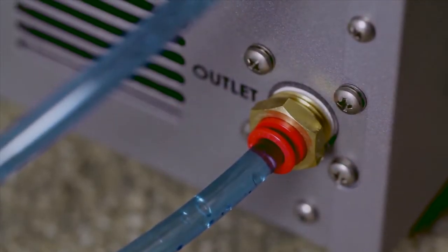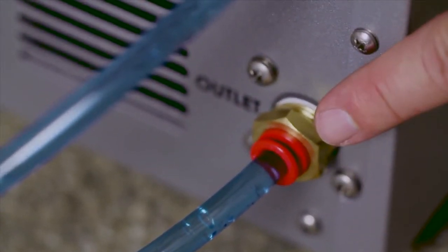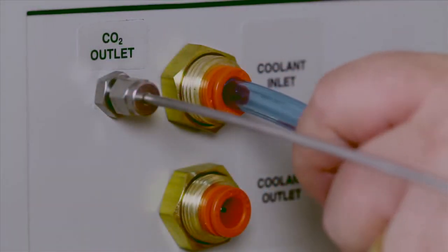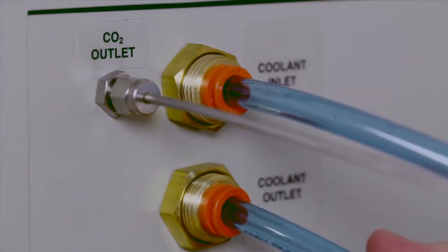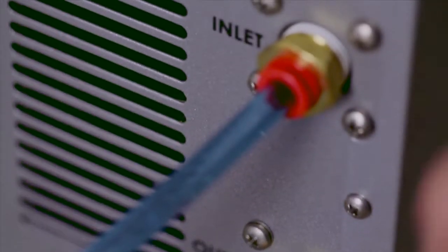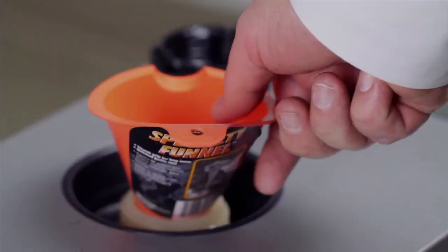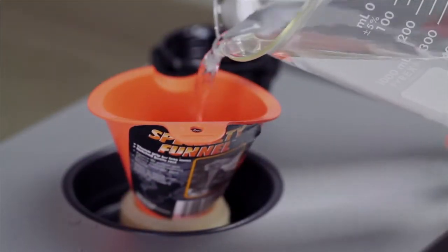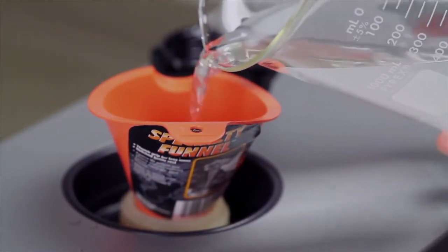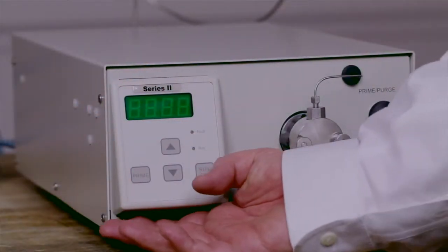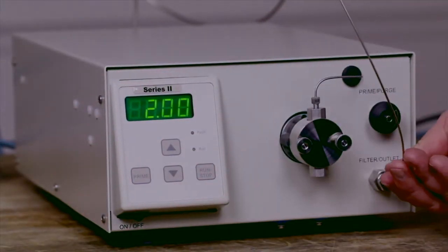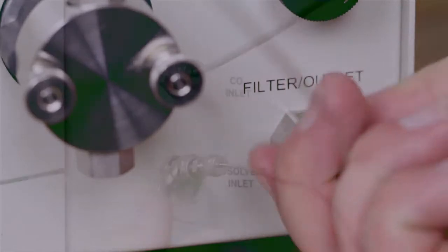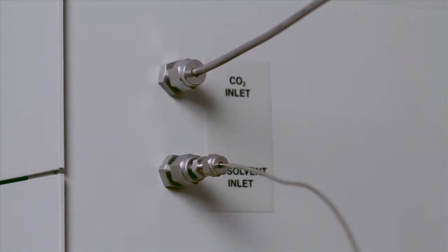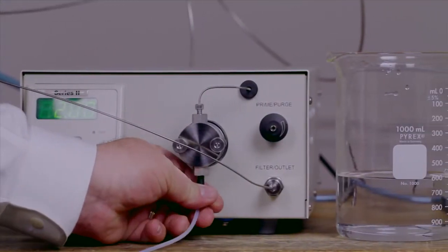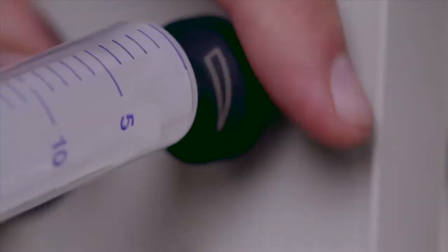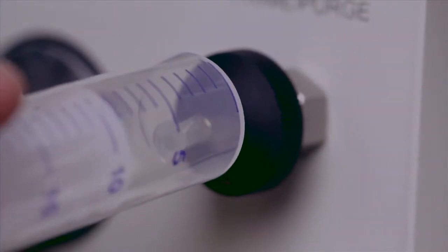Connect the chiller lines. Be certain to connect the chiller outlet to the SFT-150 inlet and the SFT-150 outlet to the chiller inlet. Add coolant, 50% distilled water, 50% ethylene glycol. The co-solvent pump, if purchased, is attached to the back of the SFT-150. Connect the solvent feed line. The pump must be primed prior to use.